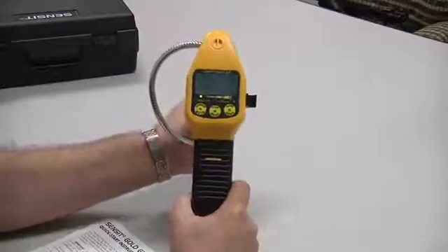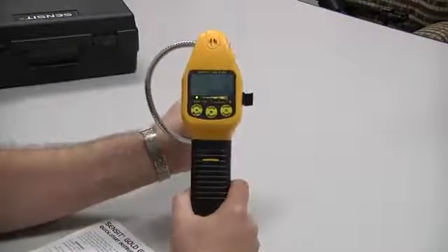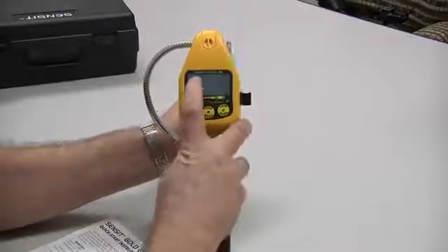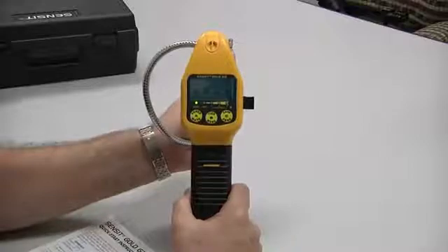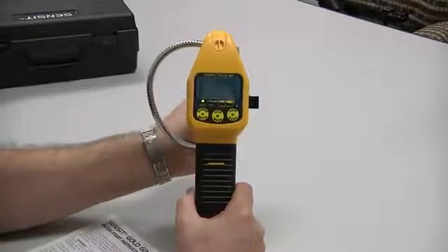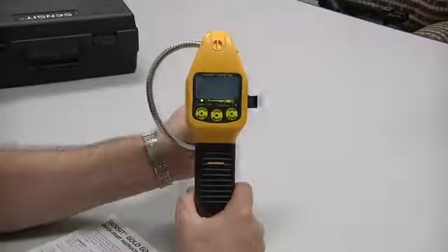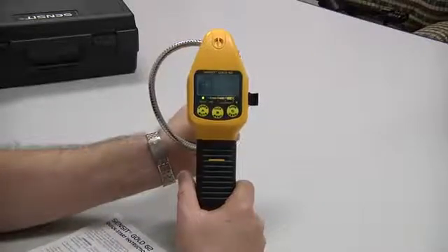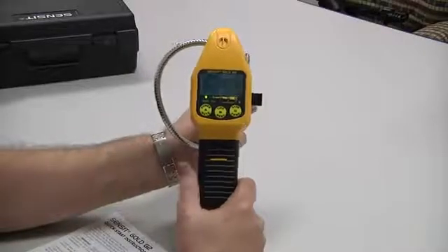Other display indications in this instrument include NSR and NSC. If during the detection of a gas other than natural gas, the instrument will display an NSC should it be a combustible gas such as propane or butane. The NSR indication will be illuminated if the gas is not of combustible nature.